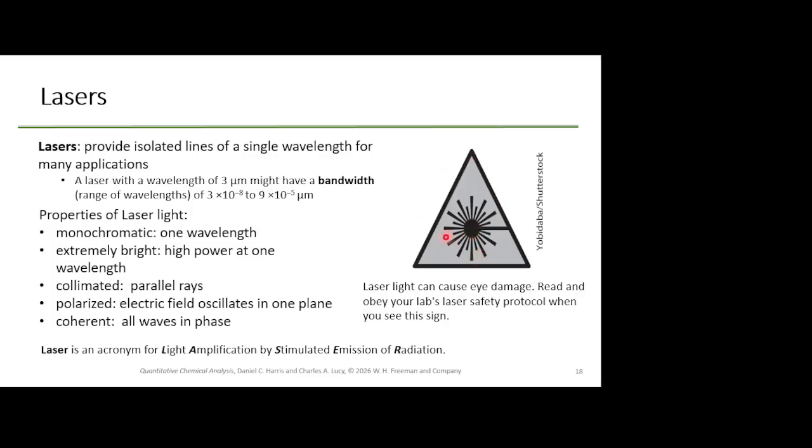Most lab grade lasers can cause blindness. So if you don't have the proper glasses for them, they're very likely going to blind you the first time you accidentally put something reflective in there, or something that causes scattering. On top of that, many lab grade lasers for things like Raman instruments are powerful enough that they can actually burn small holes in doors and stuff. Okay, they can actually burn stuff. And so if they hit anything sensitive, you're going to be really regretting it.